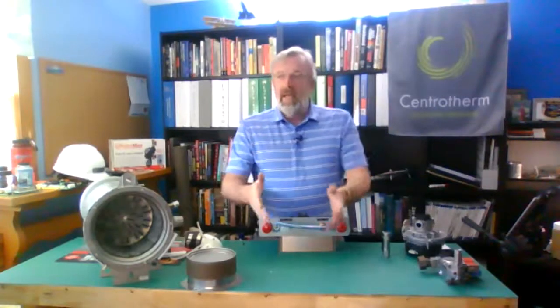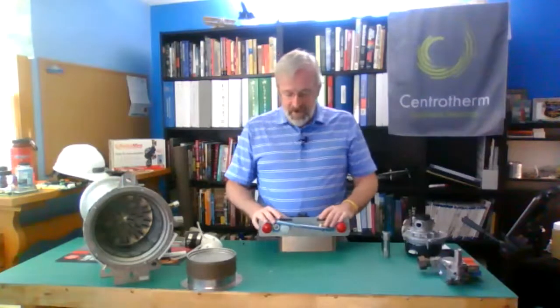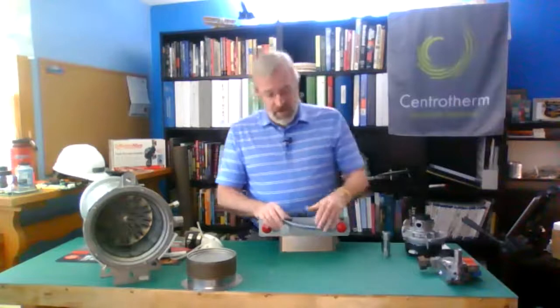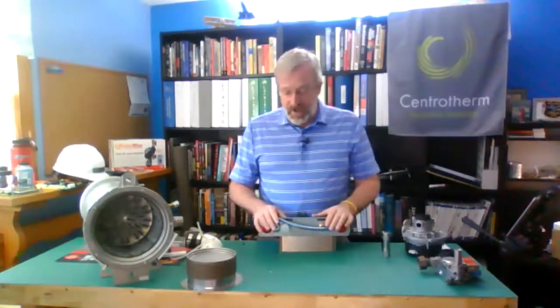The second part of that equation is there's no way the boiler will ever respond fast enough to prevent somebody being scalded if we have a transition from a heat call to a very small domestic hot water call. Figure I've got 180 degree water in here. I get a very small domestic hot water call coming through here. I could really send out some hot water and scald someone. Mixing valve, it's important. They're inexpensive. It's a good piece of insurance to have there, and it helps the boiler run better, and it actually is going to give more indoor comfort by keeping that temperature consistent.